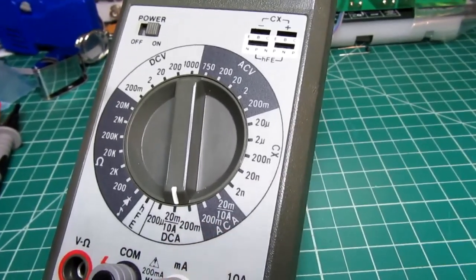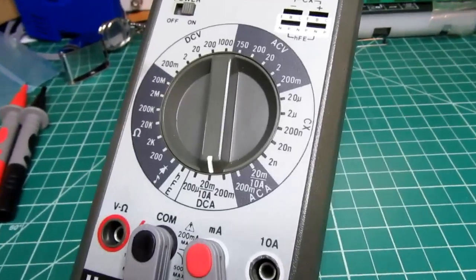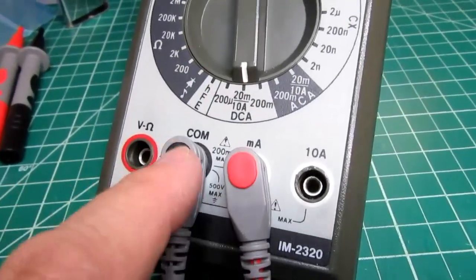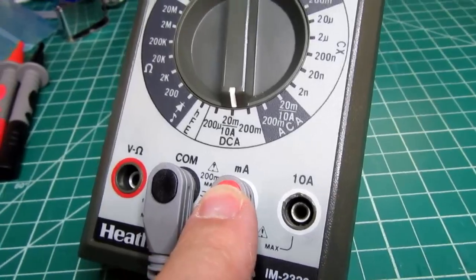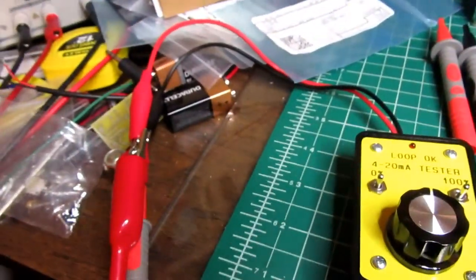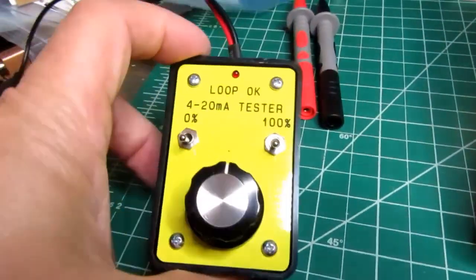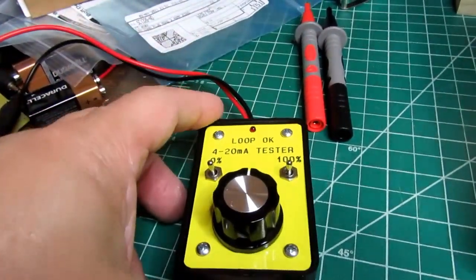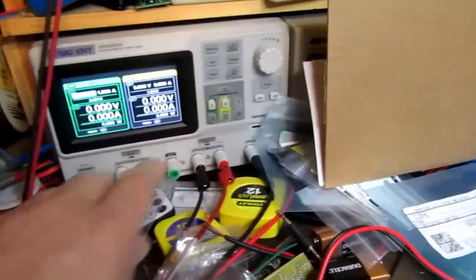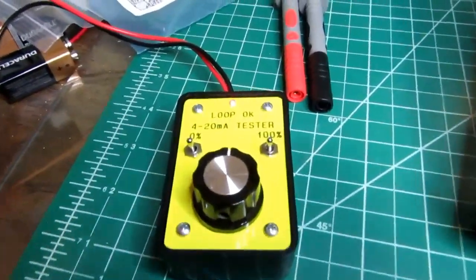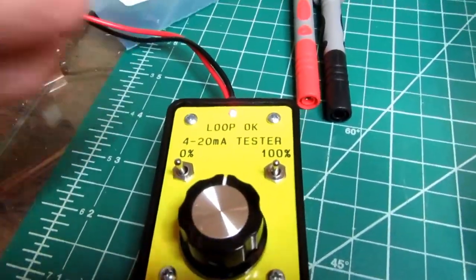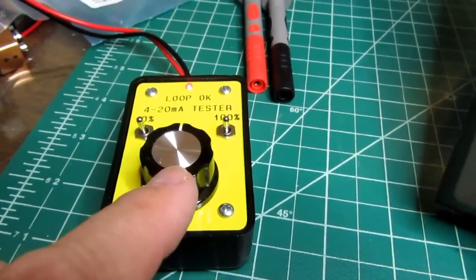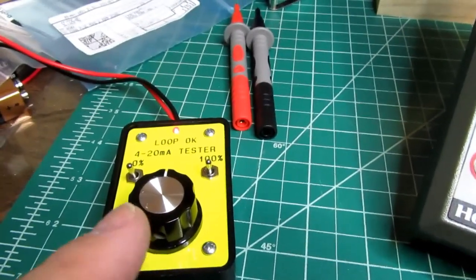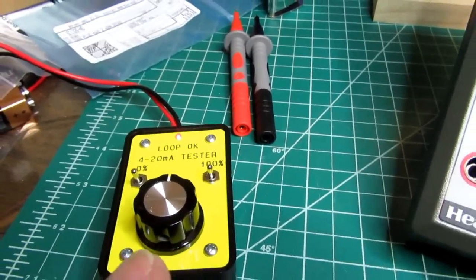So I'm not going to bother demonstrating the AC amps, but for DC amps, I have my leads plugged into common, and the milliamp range, I have those wired in series with a 4 to 20 milliamp current loop tester or transmitter, and my power supply on 24 volts DC, which when I turn it on, I'll get an indication here that the loop is okay, and it is currently selected to mid-range, which should be halfway between 4 milliamps and 20 milliamps, in other words 12 milliamps.